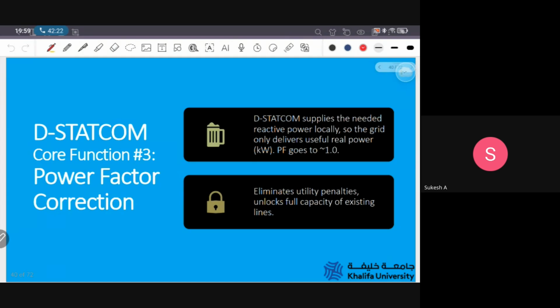And power factor correction is another main advantage. With many of our customer equipments needing reactive power, this reactive power is directly drawn from the grid because it is directly coupled with the PCC, or point of common coupling. But if we connect our distribution static compensator like a shunt, we are delivering it.